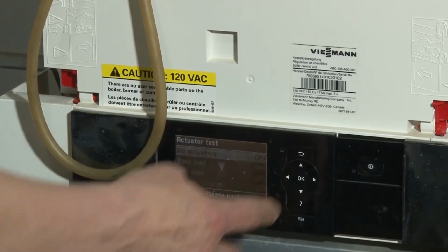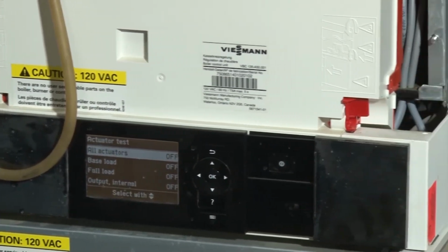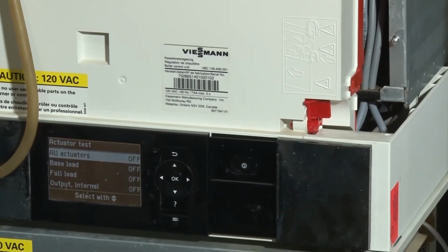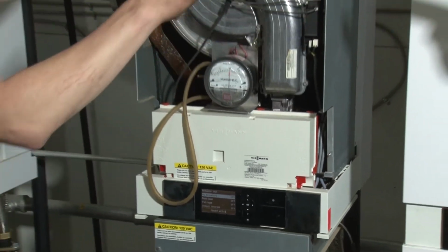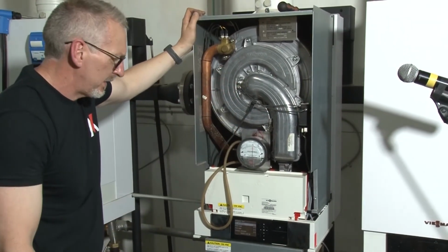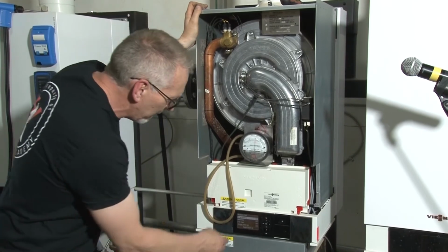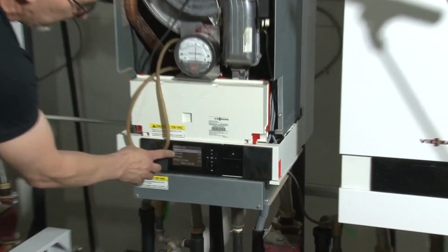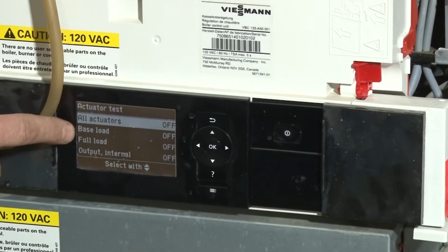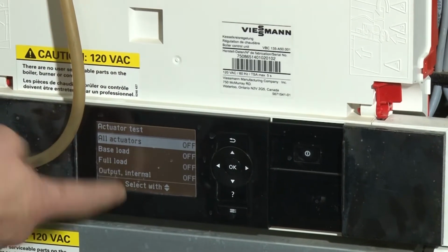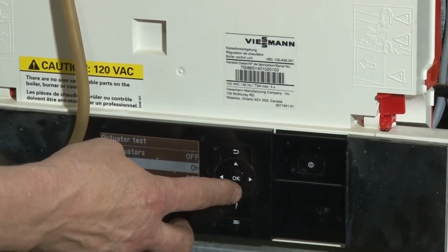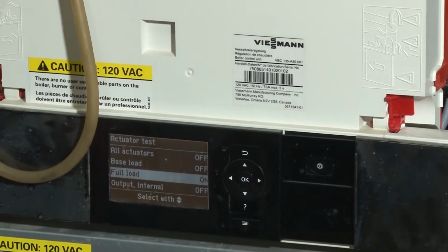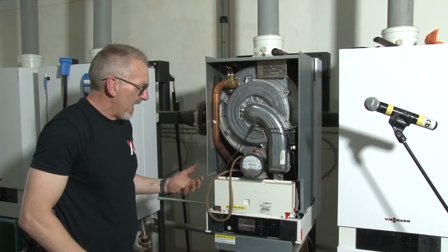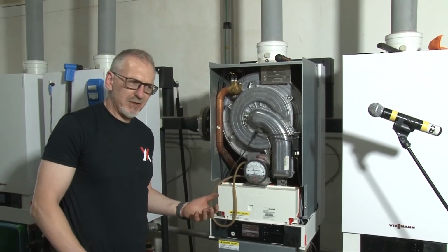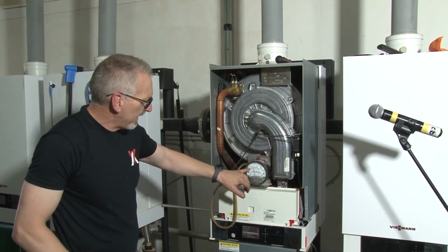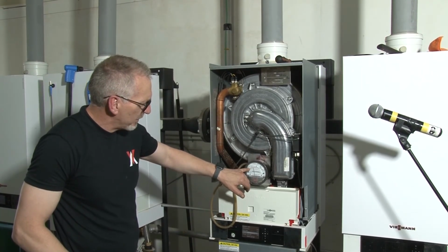But with actuator test, what happens here is, as the contractor now, I'm in control of what the burner is going to do. I don't need a load. I don't need to turn the domestic on. I don't need anything really to occur here. All I need to do basically is tell the control I want to go to low fire, which is base load, or full load, which would be high fire. In this case, I want to drive the boiler to its full load position. And now we're checking full load. So we want to check gas pressure. I don't want that gas pressure to drop below 4 inches, which is critical.